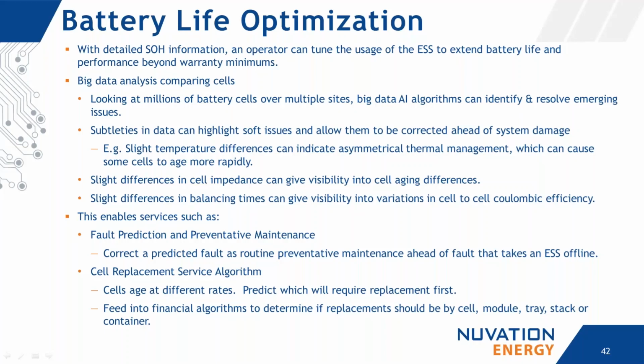Looking at the data, computers can notice slight temperature differences, which can indicate asymmetrical thermal management, and heat definitely causes cells to age faster. We can also notice slight differences in cell impedance, which can give visibility into differences in state of health and power aging. We can even look at things like balancing times, and cells that require more balancing time indicate a variation in cell-to-cell coulombic efficiency, which is again indicative of cell aging.